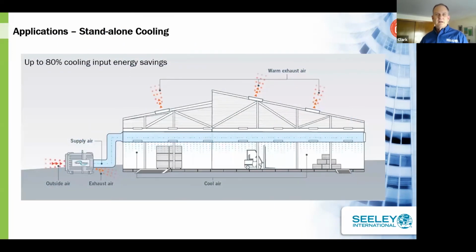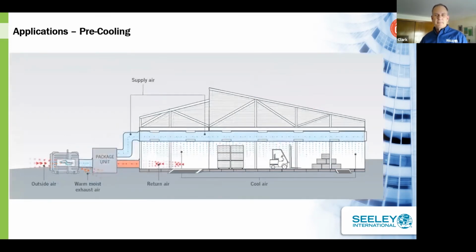Now, if we consider how you would apply these units, if we look at standalone cooling, you can see on the left, we have our Climate Wizard unit pulling in the outdoor air, cooling it down to the wet bulb or below the wet bulb, and then providing it in this ductwork in the space. And this is basically a 100% makeup air unit, cooling unit. So you have to exhaust the warm air out through the top of the building. So that's a standalone evaporative cooling.